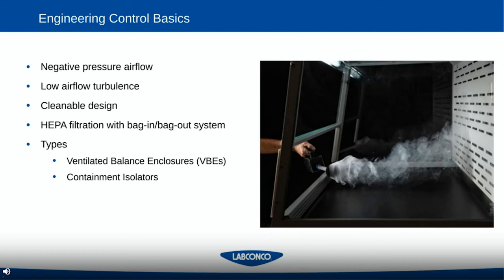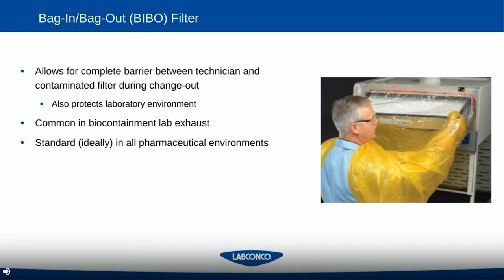These enclosures most commonly come in two formats: ventilated balance enclosures, which are open systems, and containment isolators, which are sealed systems that promote a higher level of containment. The bag-in, bag-out HEPA filtration engineering control provides an additional complete barrier when changing out saturated HEPA filters, preventing exposure of workers and the surrounding environment to hazardous APIs or powders. This should be found throughout the entire workflow where hazardous powders or APIs are used — ideally ubiquitous throughout the entire pharmaceutical process.